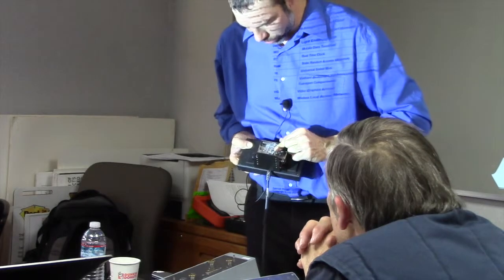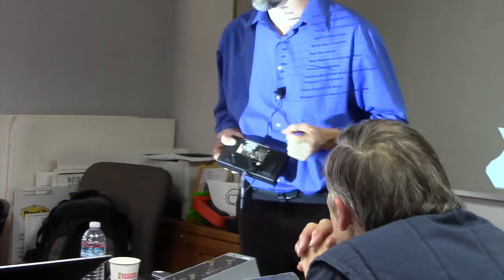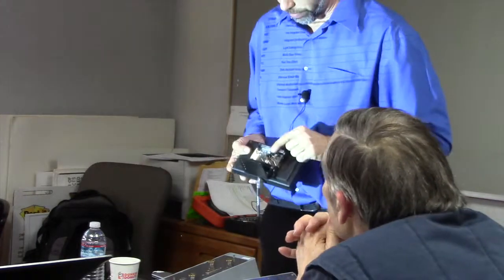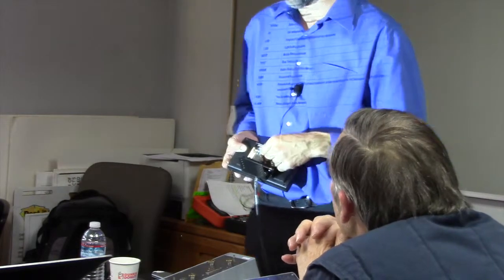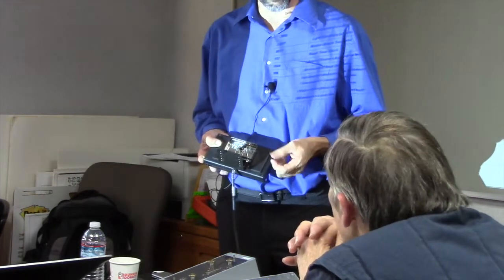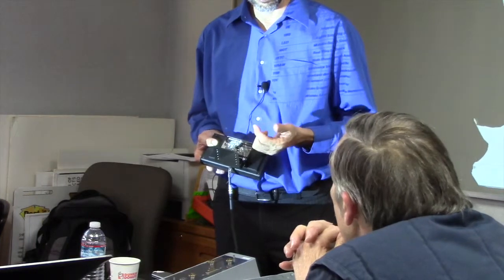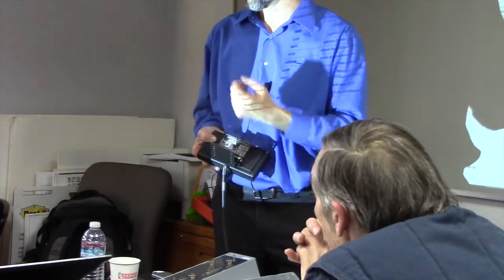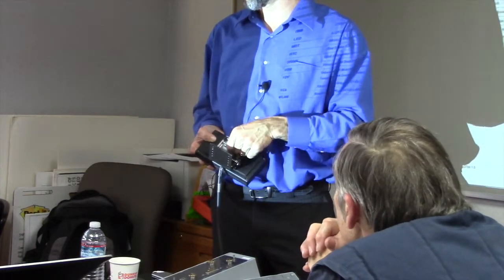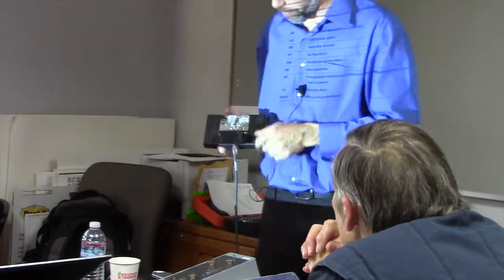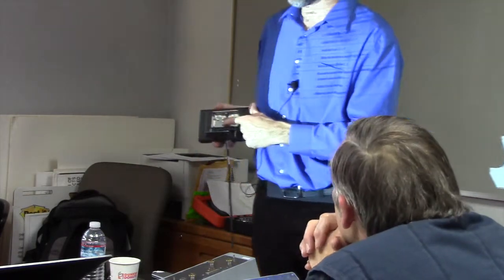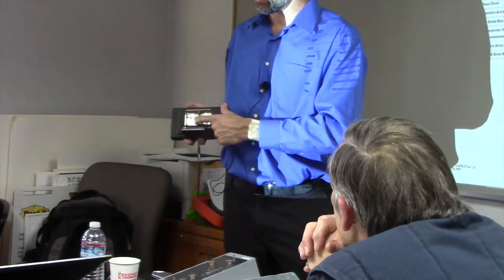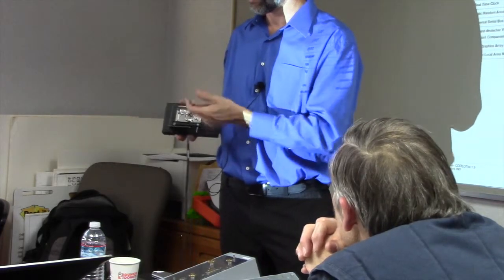If there is an issue, this is usually caught during the commissioning of the installation process, but sometimes you'll have your data crossed up. Sometimes the pin will push out if it was pushed in too hard, and you lose data, so that's something you want to check. Or over time, a pin can lose its teeth and unseat from vibration. We try to eliminate all of that with the strain relief here. That's another reason we do this in the factory, so it's a guaranteed good strain relief, and these don't wiggle as much as possible.